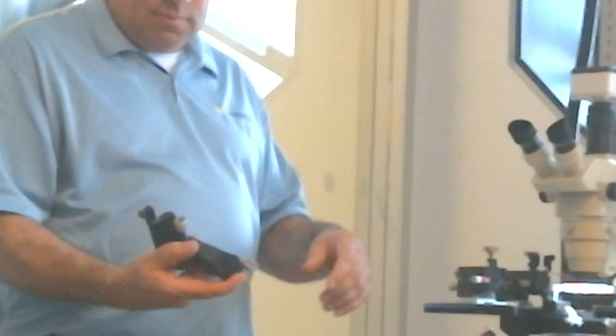There is cable tension relief here, so your RF cable and probe would be mounted here, and then your cable would come up, and you could use strain relief right there. Particularly for high frequency measurements, if your cables are moving around in relation to your probe, it can affect your measurements. With this setup, it'll keep the cable and the probe moving together, which is very important for high frequency measurements.